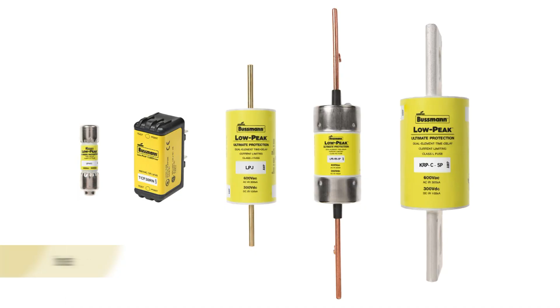Current limiting fuses enhance workplace safety by reducing the incident energy personnel are exposed to under fault conditions. Arc flash hazards may be greatly reduced when compared to using a non-current limiting overcurrent protective device, especially at 600 amps and below. Fuses can protect components and equipment from extreme thermal and magnetic forces by clearing the fault current within the first half or quarter cycle.